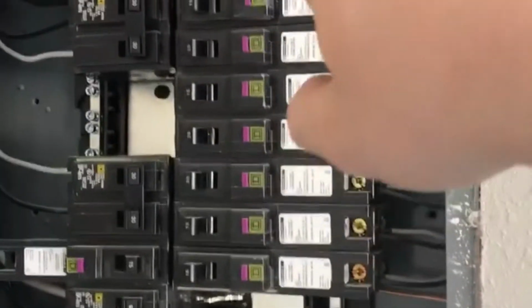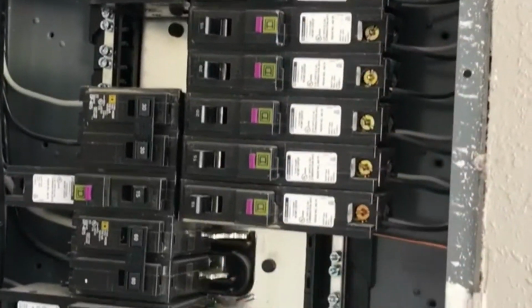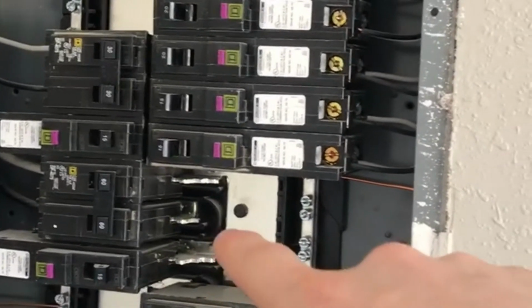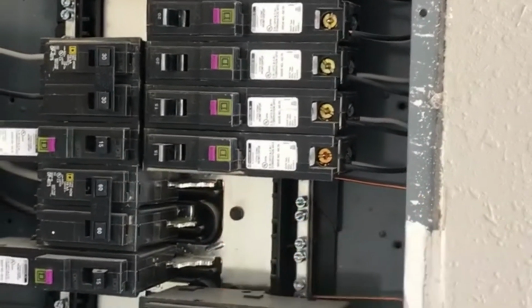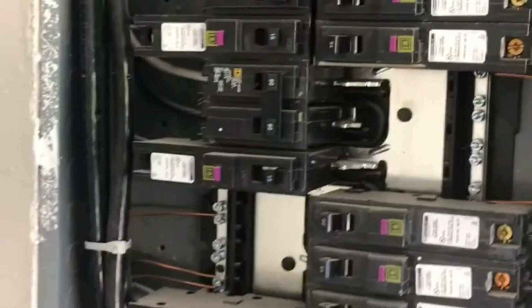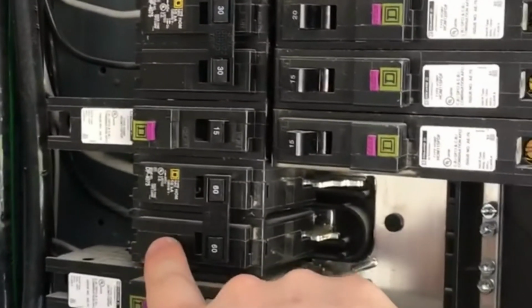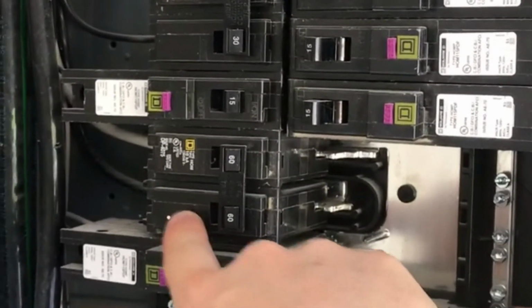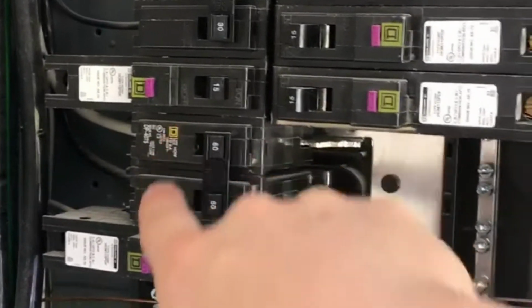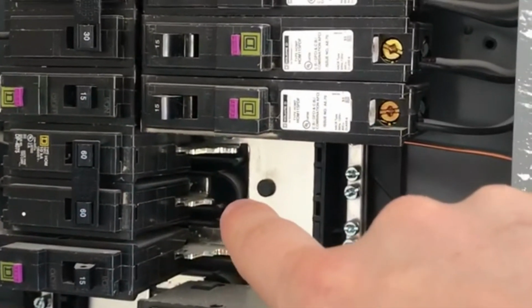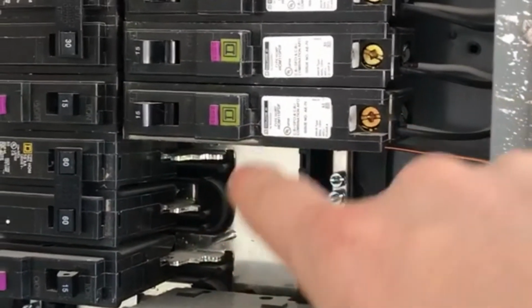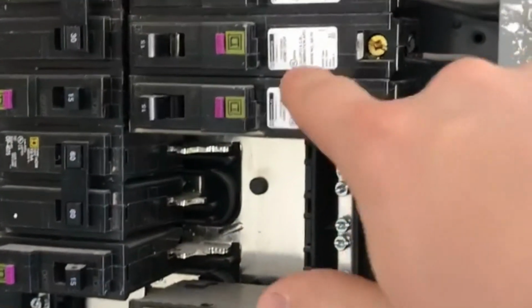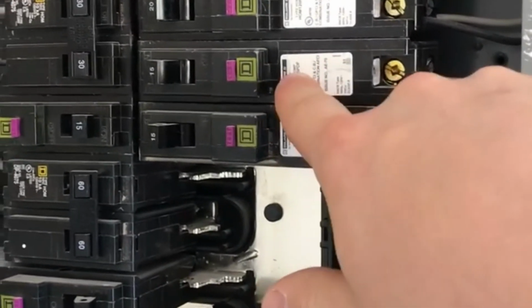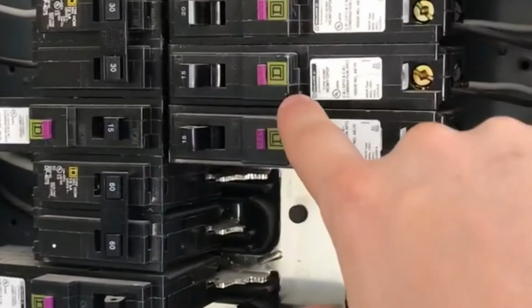In the middle is our main power bar, each one of these tabs having 120 volts. When doing 240 breakers, they take up 2 slots because they attach to 2 120 volt bars, creating 240. Single 120 breakers just utilize 1 bar.